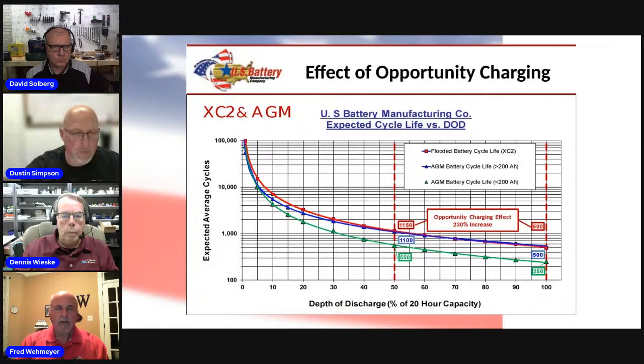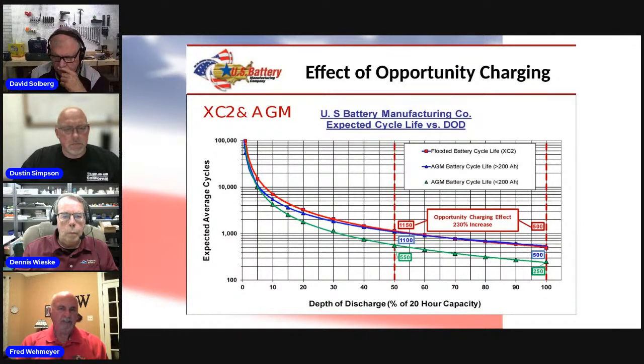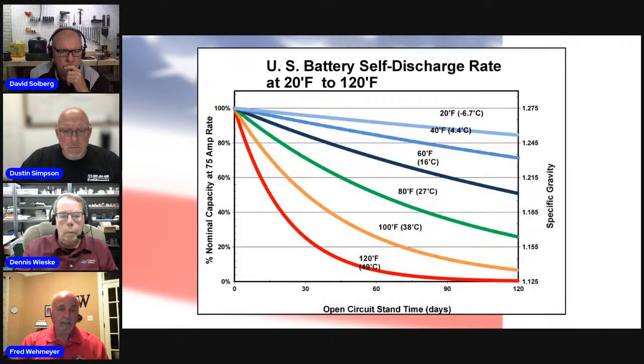And that's what we're showing here. I want to talk a little bit about the effect of opportunity charging. And people say, well, what do you mean by opportunity charging? Is that to take the place of regular charging? It's not. But if you can manage the depth of discharge through the use of opportunity charging, it pays that significant benefit that I just went through. It more than doubles the cycle life. And obviously, that chart is a logarithmic chart. That's the reason it's not linear, and you'll see the scales there are exponential. But if you can manage the depth of discharge to much less than 50%, you get a significant increase in the overall cycle life.